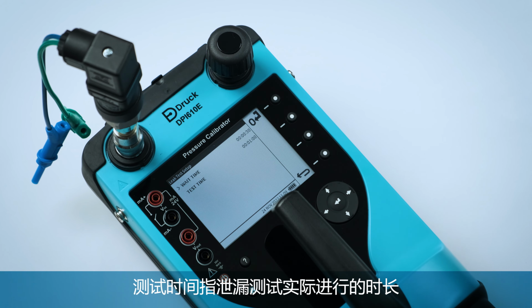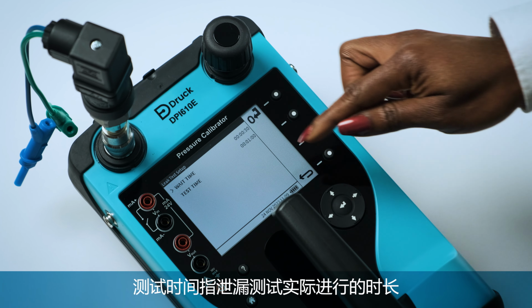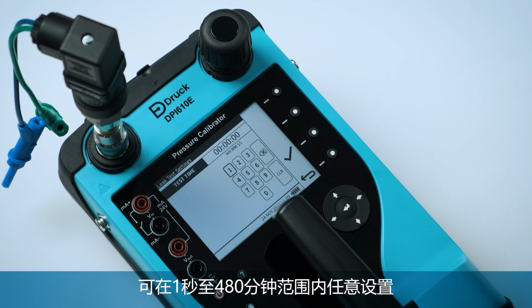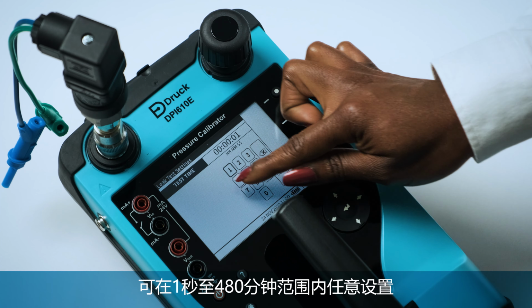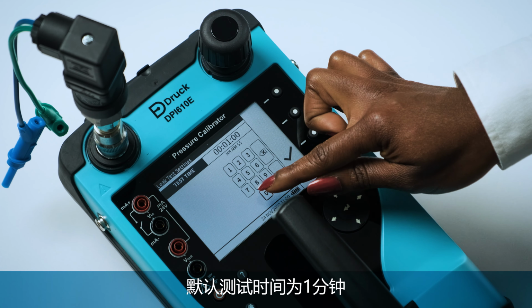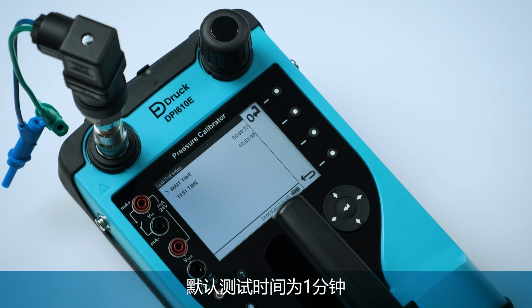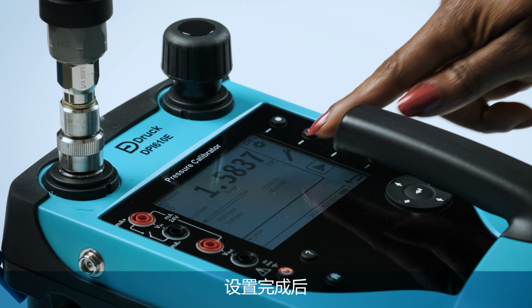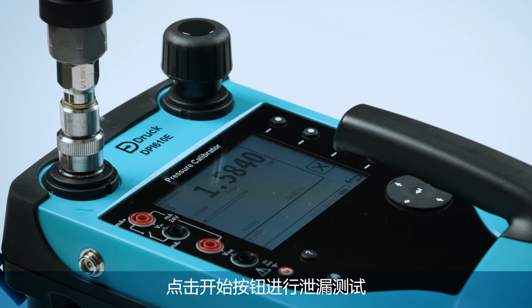The test time is the period over which the actual leak testing is carried out. This can be set to between 1 second and 480 minutes. The default test time is 1 minute. Once you're happy with your setup, press the play button to start the test.